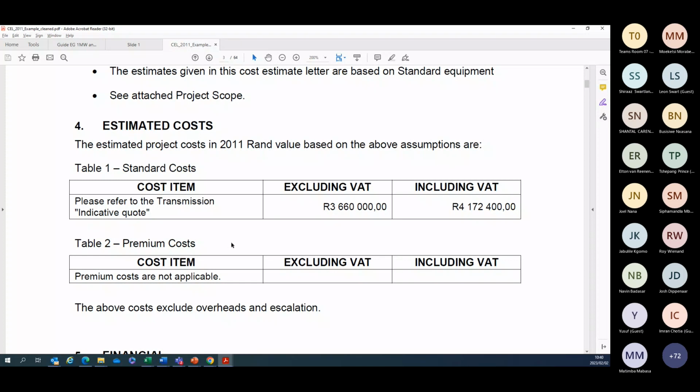But if you wanted higher reliability, they could add, for instance, another transformer in parallel to create at least an N-1 capable network or a firm network. But those customers then usually had much higher connection charges, and even their energy charges may have been higher.